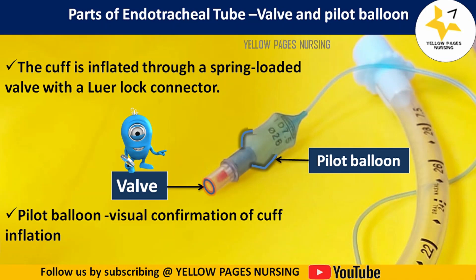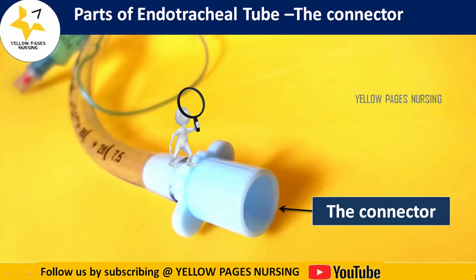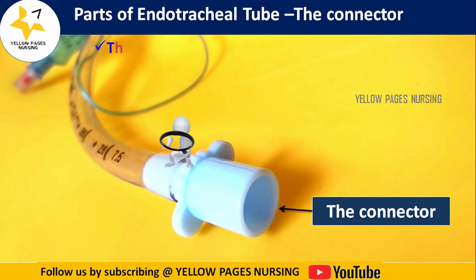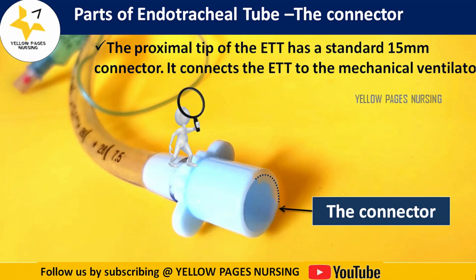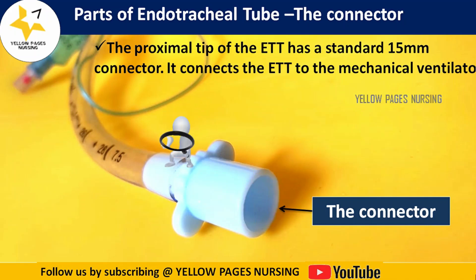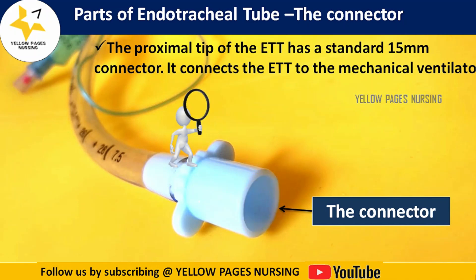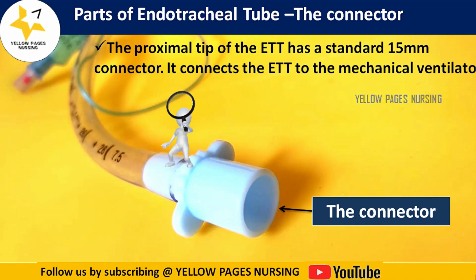Next is the connector — the proximal tip of the endotracheal tube has a standard 15 millimeter connector. This connector attaches the endotracheal tube to the mechanical ventilator through a breathing circuit. Sometimes between the breathing circuit and endotracheal tube, a catheter mount will be placed.